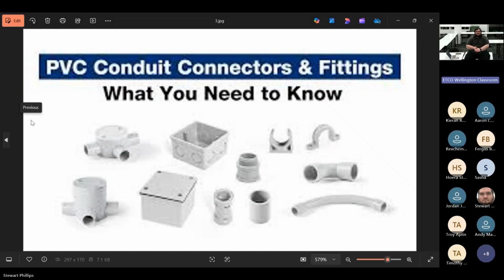Then you've got your various different types of connections, and you've got saddles and conduit clips there. So we need to make sure we're using the correct type of fitting. You can see two junction boxes there on the left. One is normal and one is a raised one. The raised one is for when you need extra space or you're running in a concrete slab and it needs to pop up.